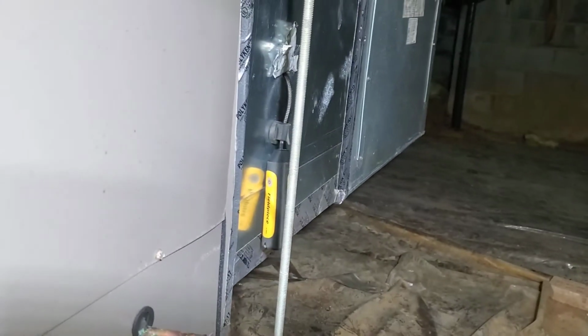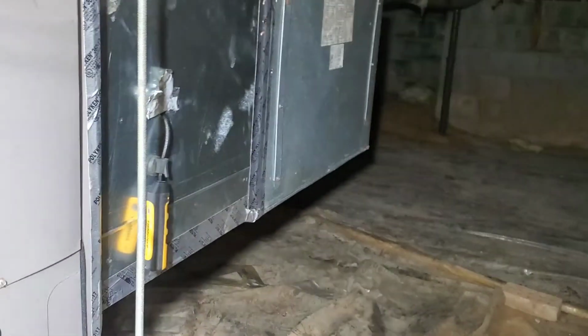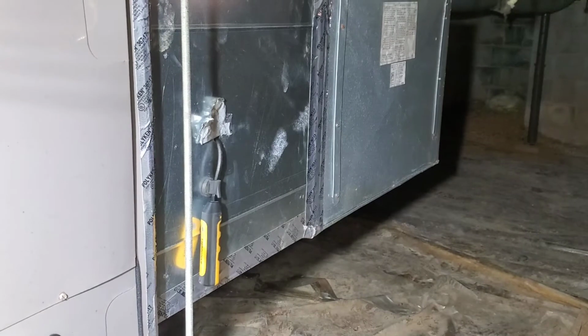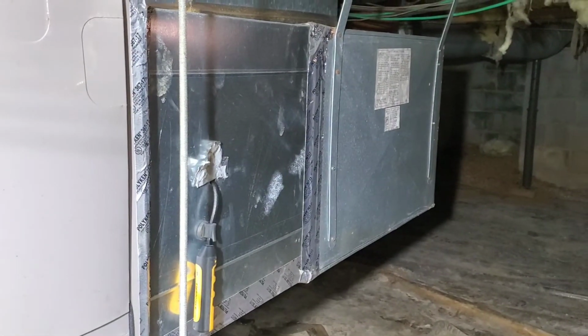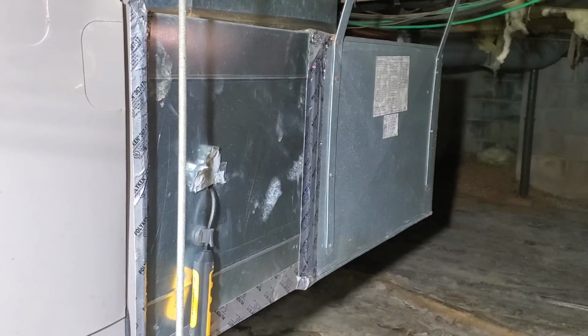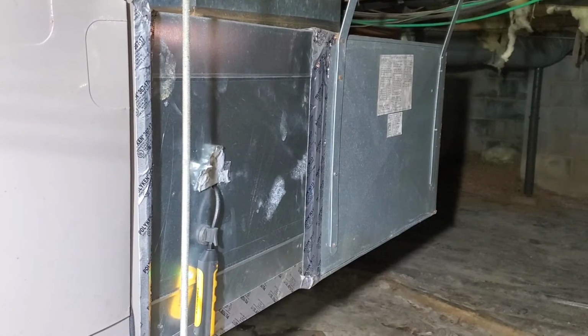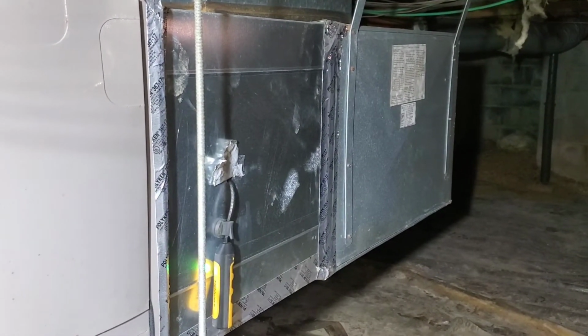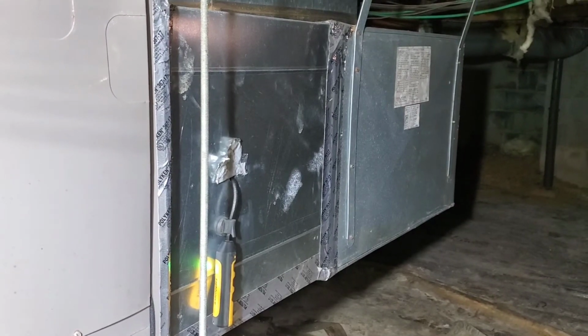The other thing is your return air sensor. Now, a lot of people want to measure their return air sensor at the grill, and that's fine, but again, when you're going through a long duct run through an unconditioned space, and let's say that duct isn't insulated very well, this is R4 duct, it's kind of old, then your return air is going to cool off.